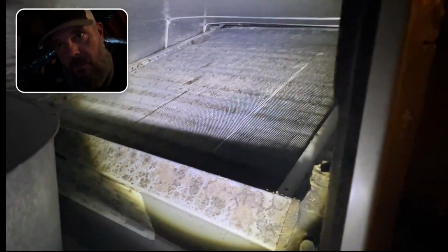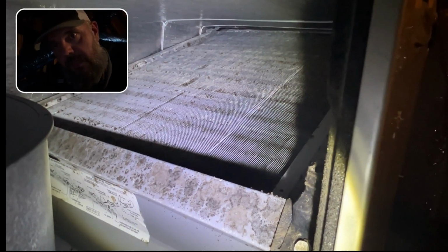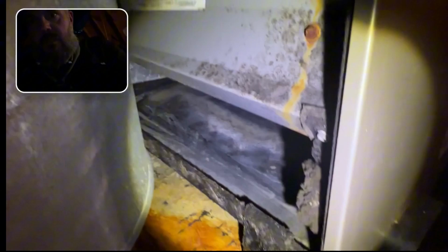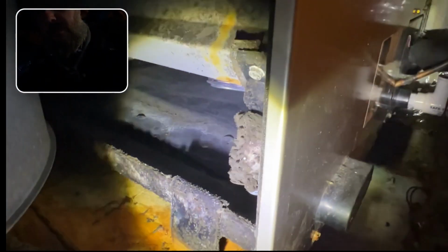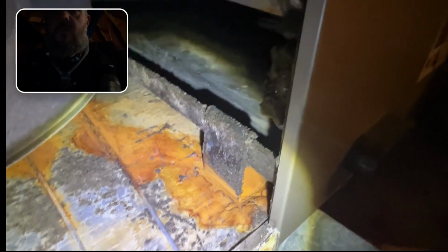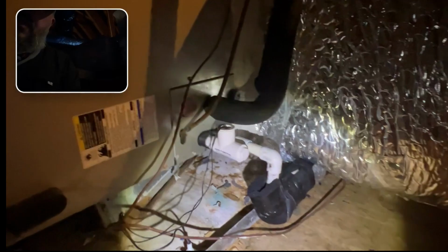And this is the blower housing with a tremendous amount of microbial growth. This is the motor, the blower motor. The wires have a tremendous amount of microbial growth. This is the coil, the evaporator coil. And as you can see, this is the outlet side of the coil. So the inlet side is probably a lot worse than this side. And as you can see, we have quite a bit of microbial growth here. I mean, it's pretty substantial. We have some water damage, obvious signs of condensation issues, drain issues. Another thing with this unit is this main drain line is actually double trapped, possibly even triple trapped because of a belly in it. I'm surprised it's even draining.